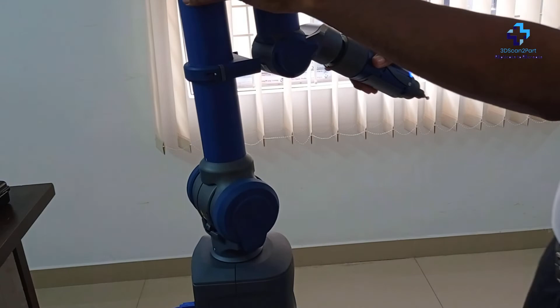Let us see the contents of the probe kit case. So this is the probe 6 mm ball. That is, the ball size is 6 mm diameter. Here we have probe 3 mm ball, which is much delicate, and we use the 6 mm ball probe most often. This is the compensation sphere and this is a compensation cone. Both of them are used for calibrating the probe before we start inspection.